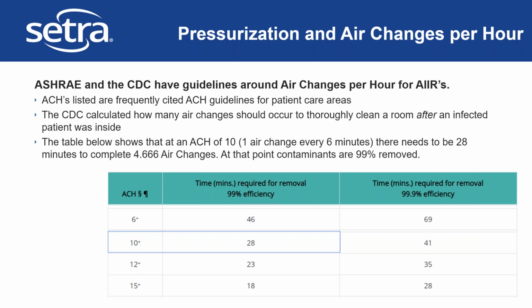If you change out the volume of air a certain number of times, the CDC has calculated that will bring you to 99% or 99.9%, depending on where you're looking in the table, of efficient removal of the contaminants in the air. So this is really, regardless of many of the other factors in your space, all you need to know is the air change per hour rate that you are running at, and then you can use this table to determine how long in between the infected patients you would want to leave to have those air changes per hour running, and for you to be confident that you have effectively removed contaminants to either 99% or 99.9%, again, up to your preference there.